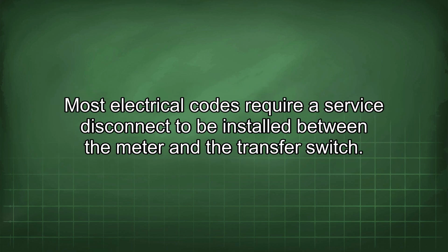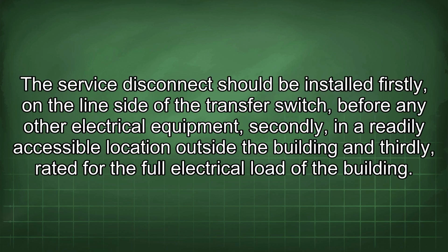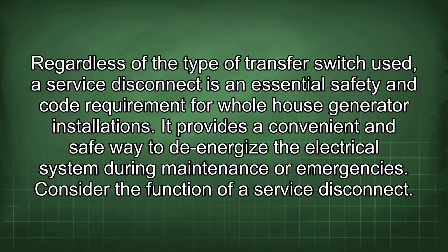Most electrical codes require a service disconnect to be installed between the meter and the transfer switch. The service disconnect should be installed firstly on the line side of the transfer switch, before any other electrical equipment, secondly, in a readily accessible location outside the building, and thirdly, rated for the full electrical load of the building. Regardless of the type of transfer switch used, a service disconnect is an essential safety and code requirement for whole house generator installations. It provides a convenient and safe way to de-energize the electrical system during maintenance or emergencies.